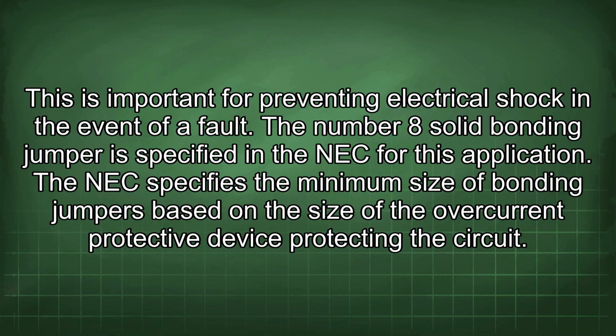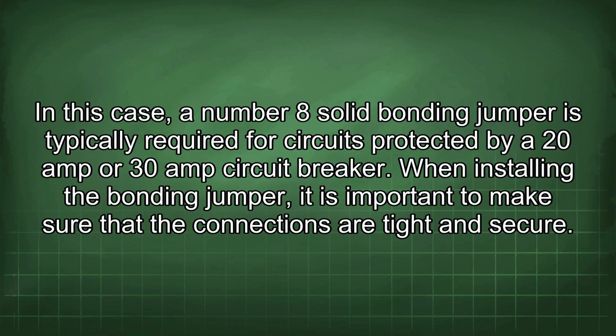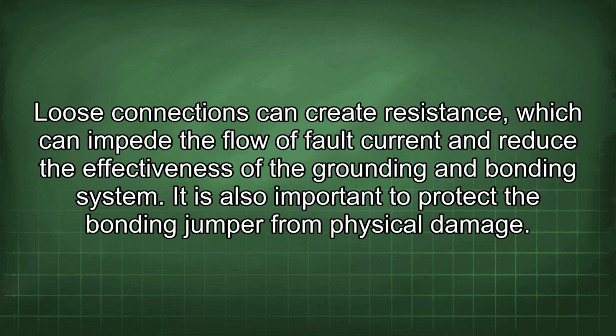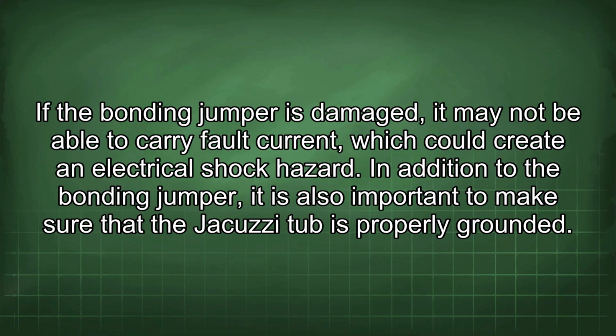The number 8 solid bonding jumper is specified in the NEC for this application. The NEC specifies the minimum size of bonding jumpers based on the size of the overcurrent protective device protecting the circuit. In this case, a number 8 solid bonding jumper is typically required for circuits protected by a 20 amp or 30 amp circuit breaker. When installing the bonding jumper, it is important to make sure that the connections are tight and secure. Loose connections can create resistance, which can impede the flow of fault current and reduce the effectiveness of the grounding and bonding system. It is also important to protect the bonding jumper from physical damage. If the bonding jumper is damaged, it may not be able to carry fault current, which could create an electrical shock hazard.